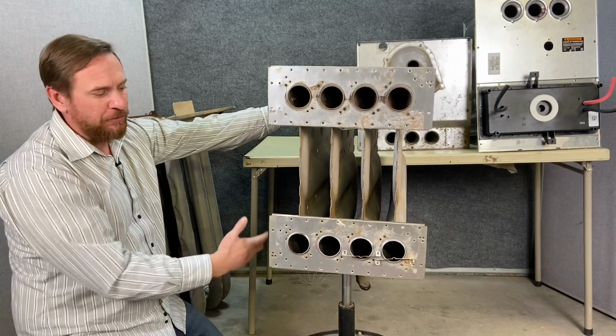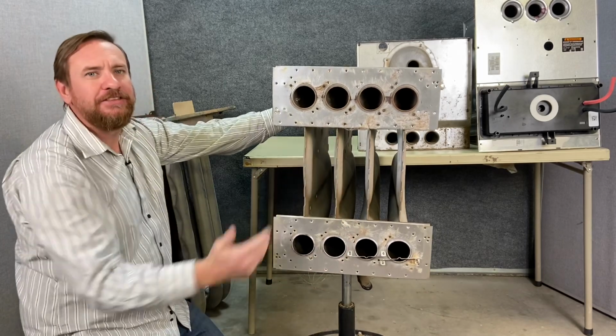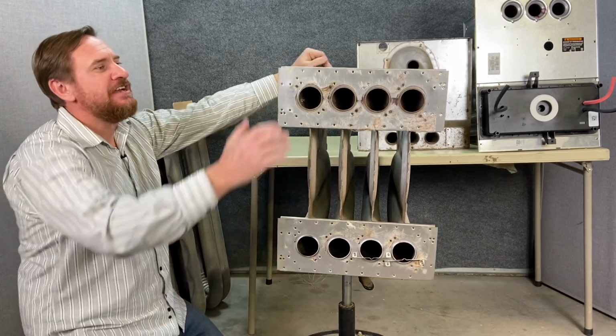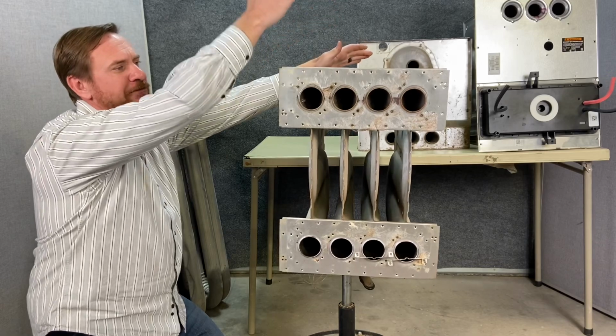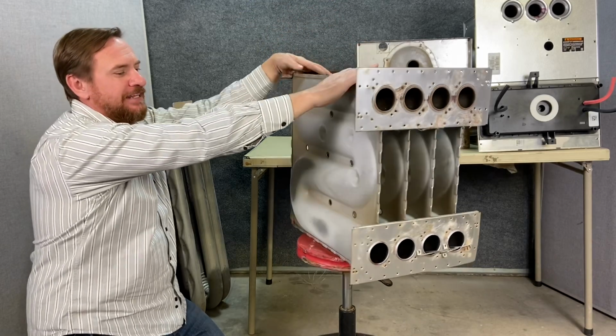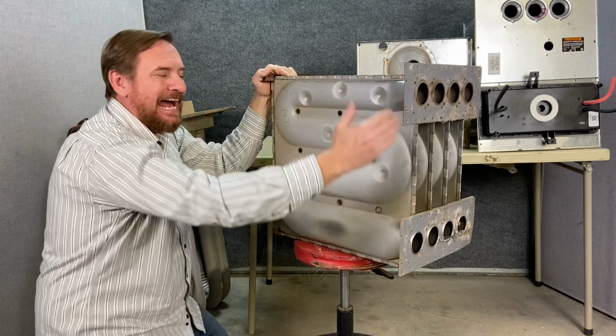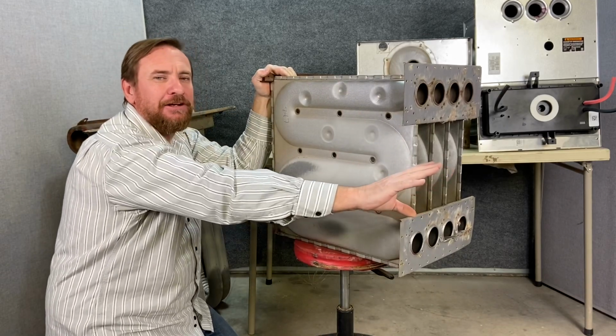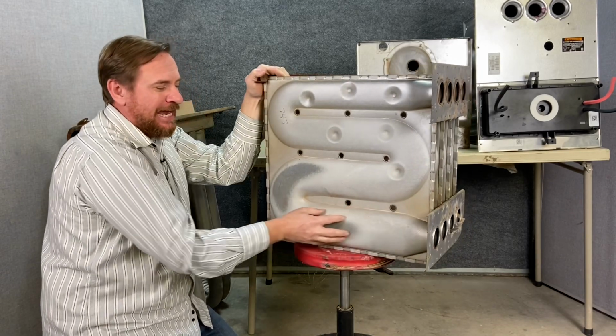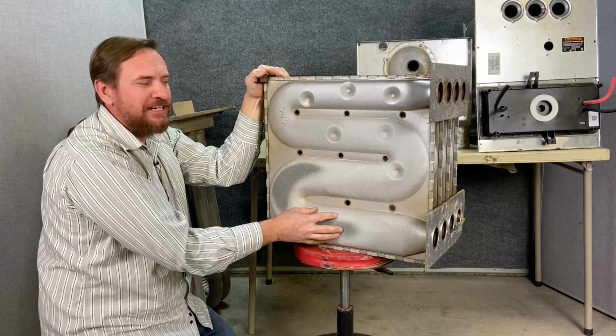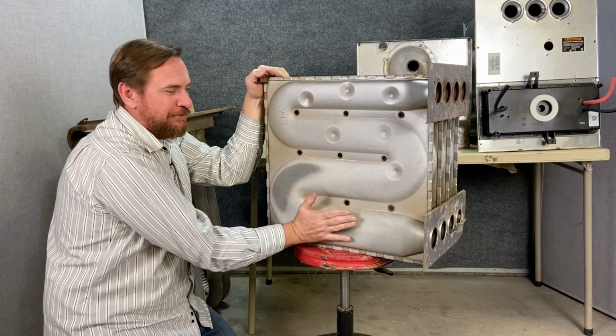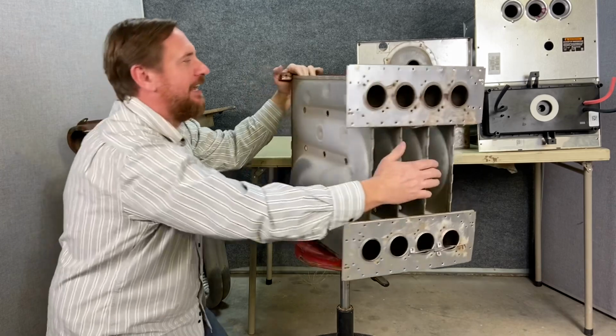Another thing we would do is pull the blower and we'd look in from underneath to check the condition of this heat exchanger. And the evaporator coil that sat on top is notorious for leaking water. So again, the heat exchanger, on the outside of this panel, we had all of our combustion area. The actual flames would burn inside of the heat exchanger, but the heat exchanger kept the flames separate from the air in the house.